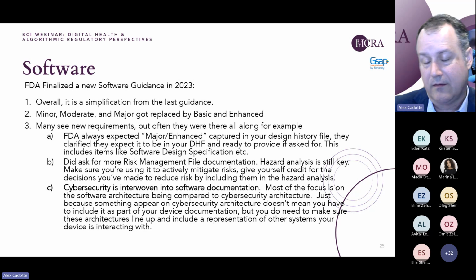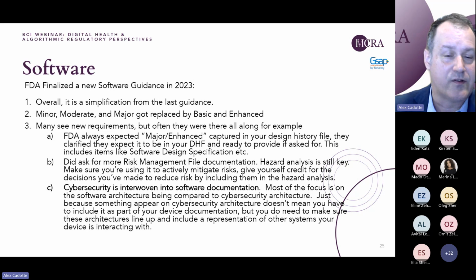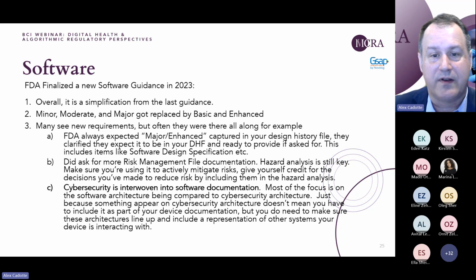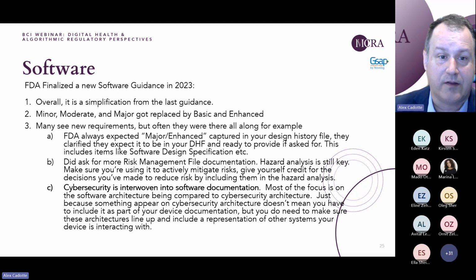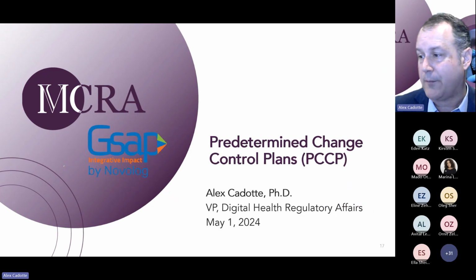Another thing to consider, which is often a major point, is that FDA does compare your software architecture to your cybersecurity architecture. There may be subtle differences between these two, but it doesn't necessarily mean that everything in your cybersecurity architecture is part of your medical device. But FDA does need to understand how your medical device interacts with other systems and how it's potentially interoperable with other medical devices and systems and basically the outside world. Generally speaking, those are the high-level considerations for software and cybersecurity that I wanted to talk about.